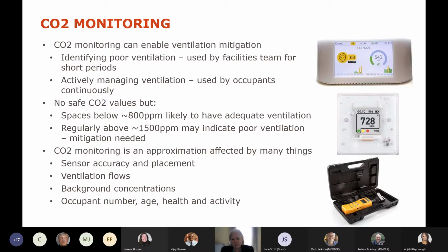We have to remember it's an approximation. It's not an exact number, not a regulatory number, and it doesn't measure ventilation rate. It gives you a marker for what the ventilation is likely to be, but it depends on your sensors—you should always use NDIR sensors—and depends on where you position them. It will depend on the design of the ventilation, on background concentrations, so urban spaces will have higher values than rural spaces, and it depends on what the people are doing in that space and who they are.